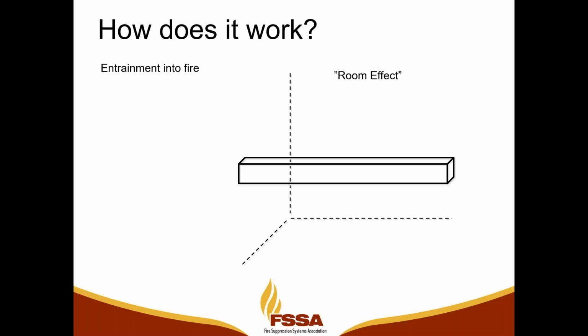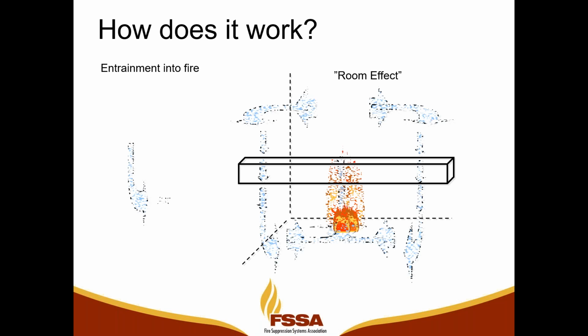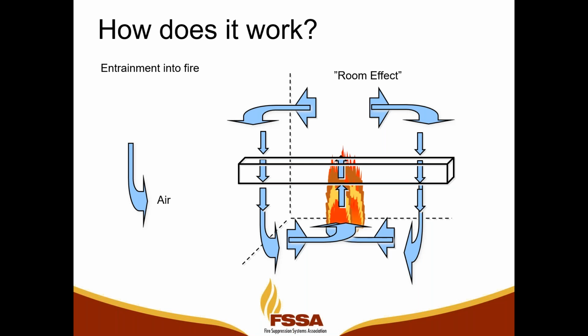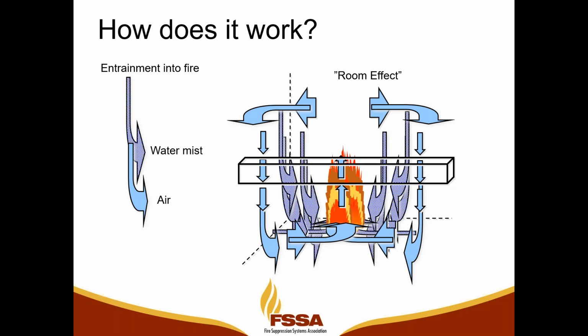So how does a water mist system work? First you have a fire. Then as the fire burns, it's going to start pulling air into the fire to feed it. As the air gets into the fire, it's providing the fuel and everything else for the fire to grow. And then when you discharge your water mist system, the small molecules of water, of the mist, are entrained into the airflow, the air intake of the fire, therefore penetrating the core. As those molecules get into the fire, they expand about 1,700 times, therefore creating steam at the fire core, and putting the fire out by basically choking off the fuel and the oxygen source at the core of the fire only. It will not reduce the oxygen levels within the space itself on a homogeneous basis. Next slide.